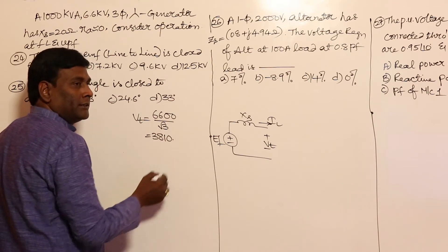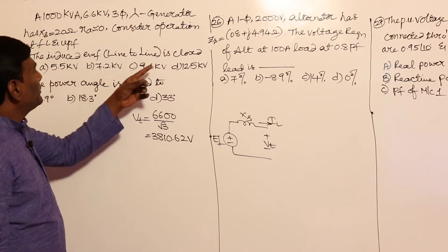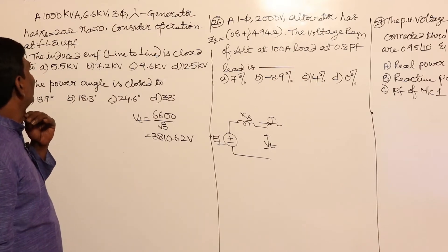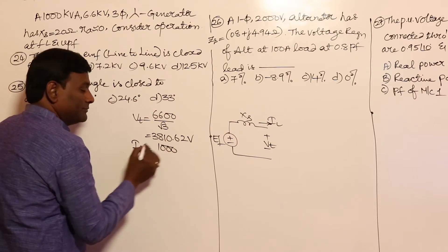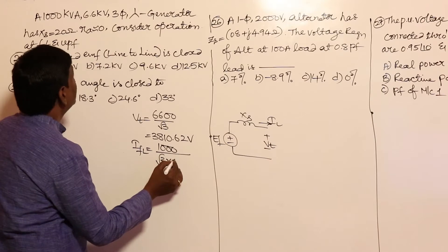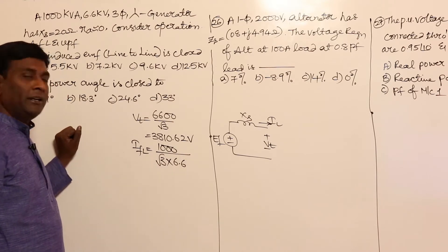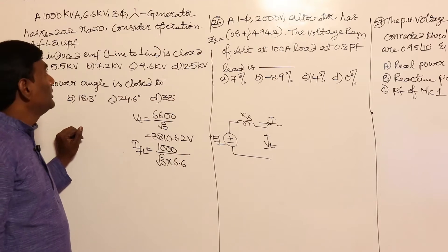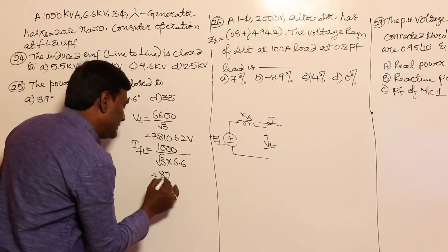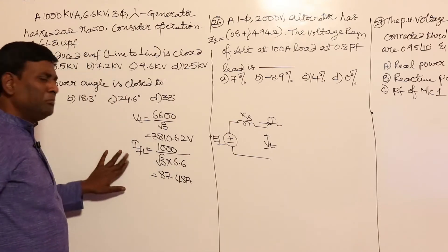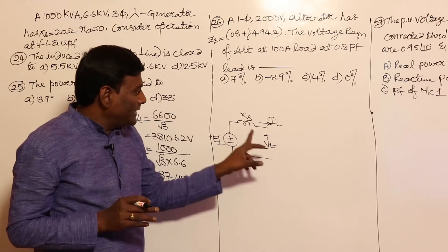Vt per phase comes to 3810.62 volts. Now, the induced EMF line-to-line — consider operation at full load, unity power factor. Full load current equals 1000 kVA divided by root 3 times 6.6 kV, which gives 87.48 amperes. Since it is star connected, line current equals phase current. We calculate Ef: Vt plus drop equals Ef.